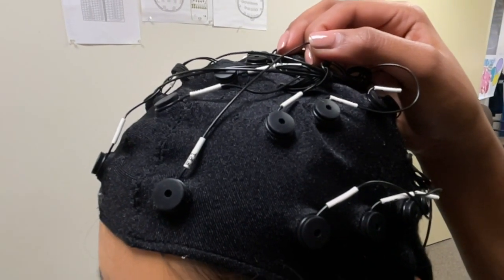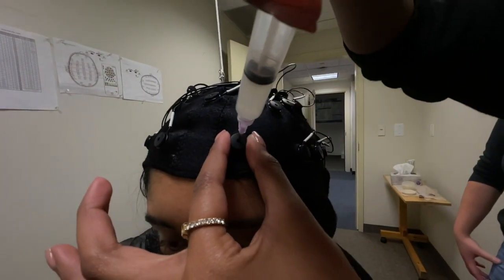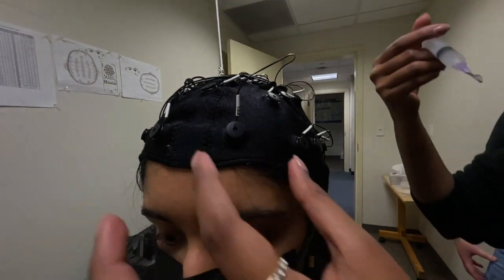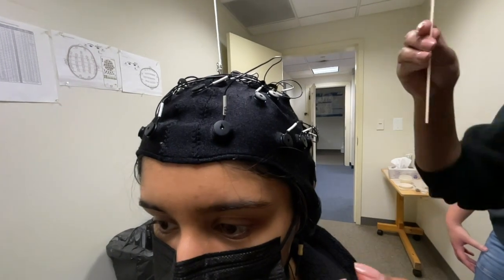To further lower the impedance on FP1 to below 5 kiloohms, fill the FP1 electrode with gel and work it down. If it comes down quickly and easily, it is a good indicator that the impedance at the left reference junction is low.